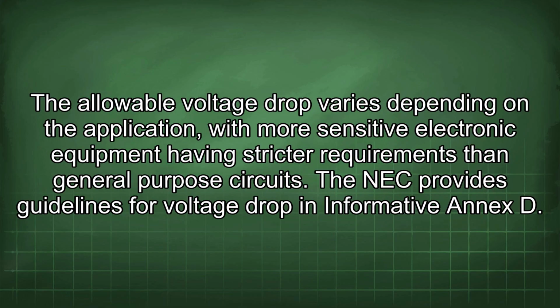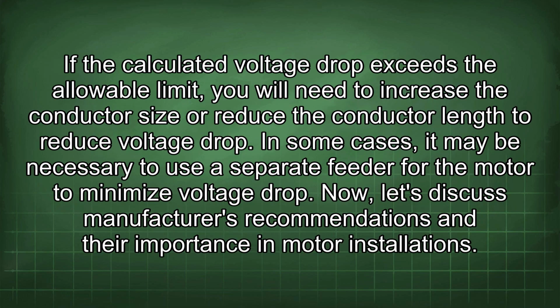The allowable voltage drop varies depending on the application, with more sensitive electronic equipment having stricter requirements than general-purpose circuits. The NEC provides guidelines for voltage drop in informative Annex D. If the calculated voltage drop exceeds the allowable limit, you will need to increase the conductor size or reduce the conductor length to reduce voltage drop. In some cases, it may be necessary to use a separate feeder for the motor to minimize voltage drop.